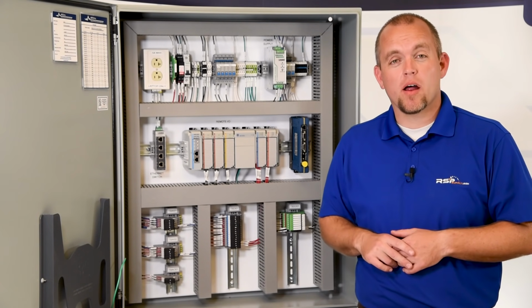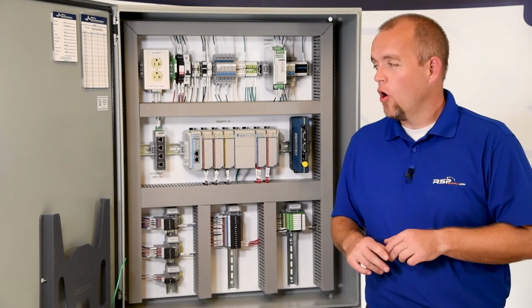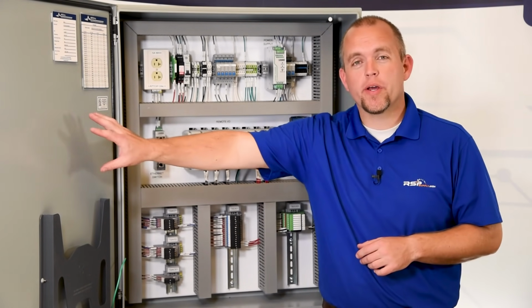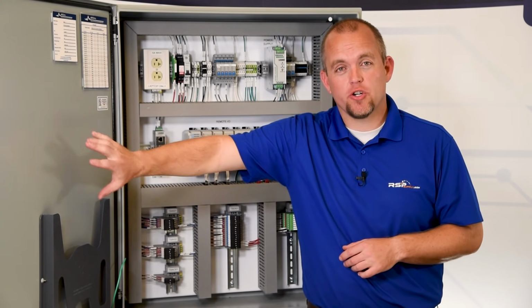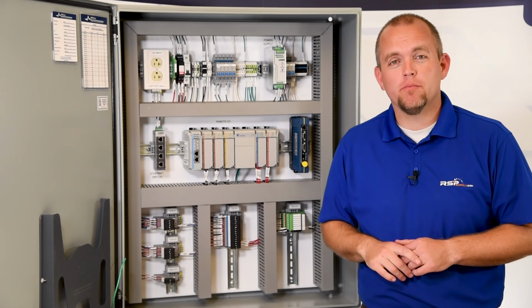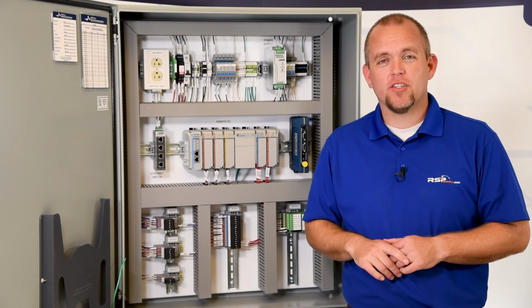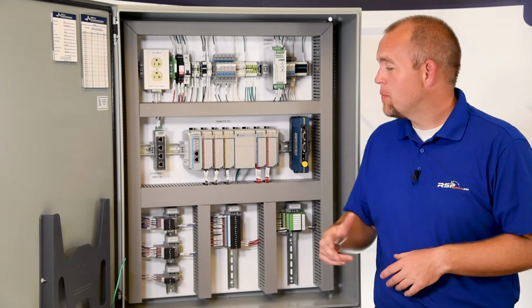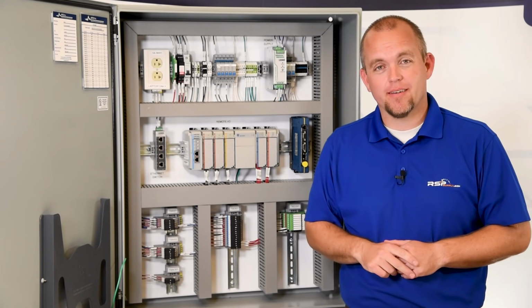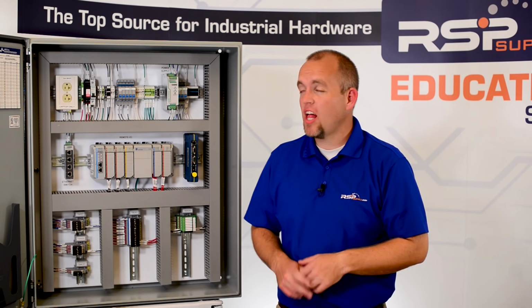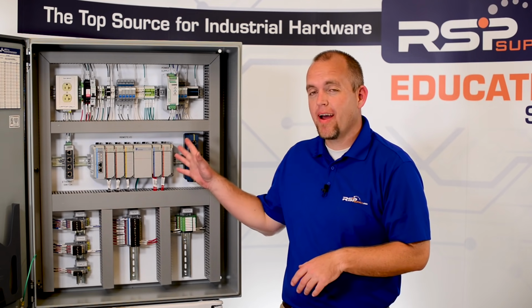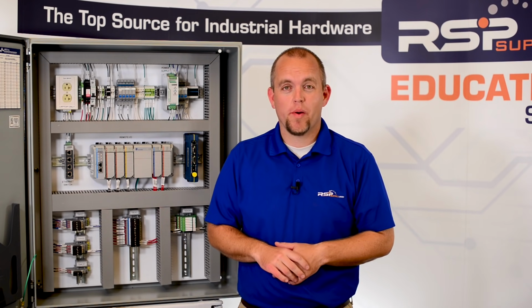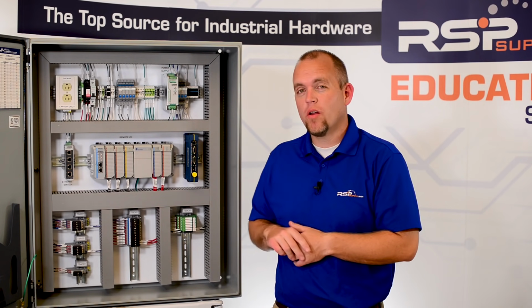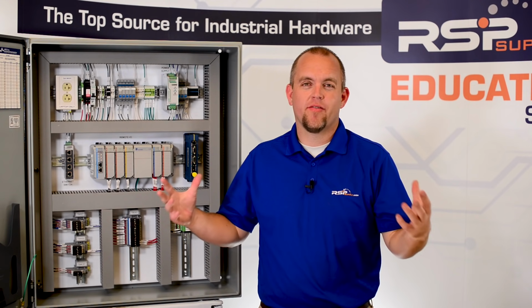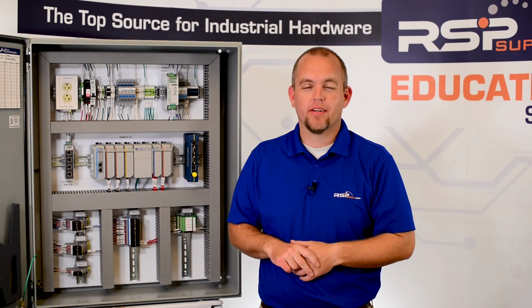It is common to make modifications to electrical enclosures. One common modification is to mount what we call an HMI to the door of the enclosure. HMI stands for Human Machine Interface. It allows us to view and manipulate the data being sent and received by the PLC. As you can see, there's a lot that goes into the design and fabrication of an industrial control panel. However, this is just one variation of thousands of different ways that we can build and fabricate control panels.